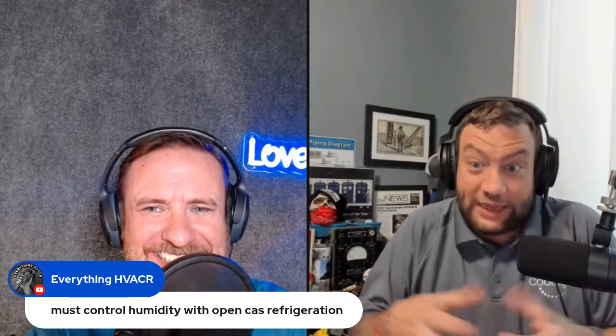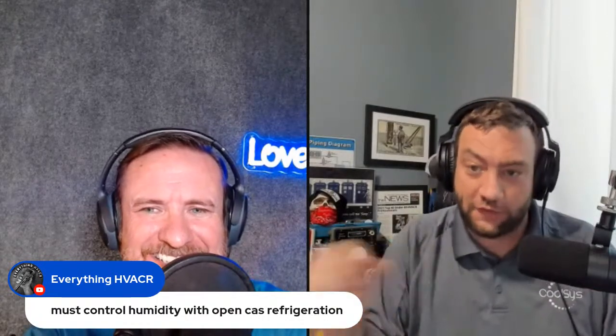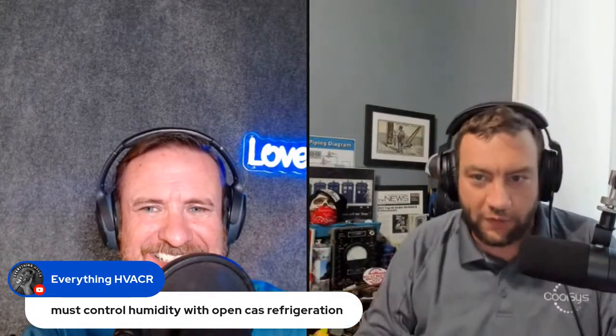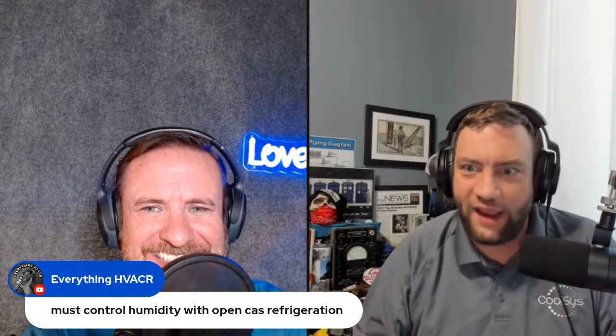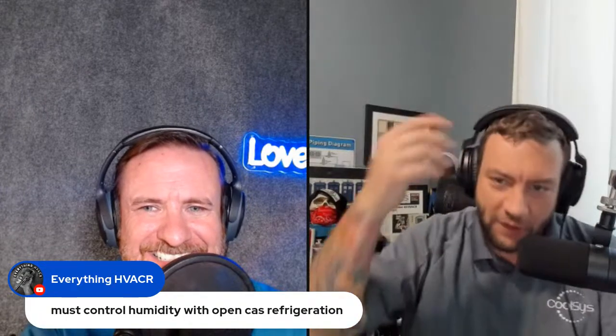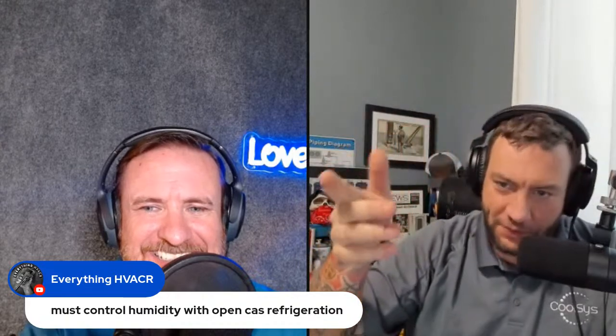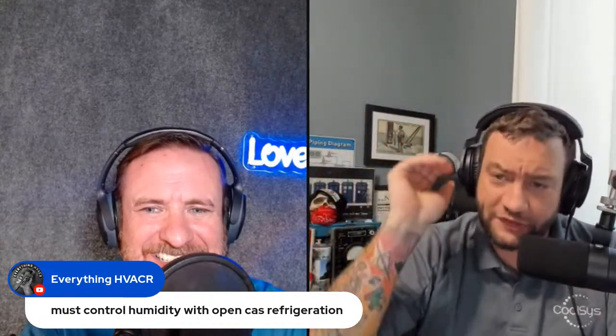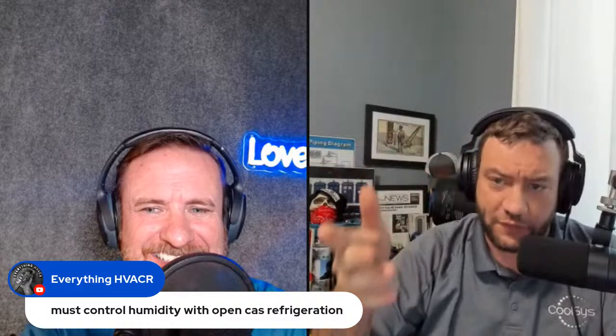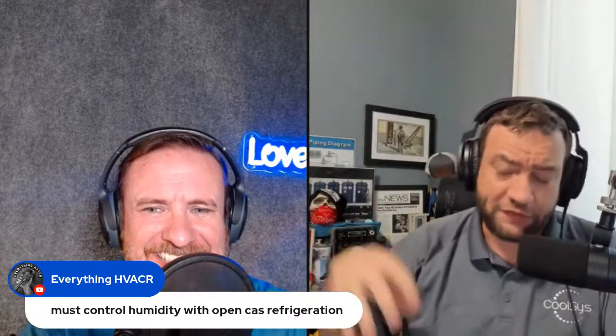It was actually inflated, and you could see it in the air along the seams. I saw metal foil tape over every single seam. I'm like, why is every single seam leaking? So I go up, there's a VFD booster they put on there just to get some additional pressure in this one facility, because it's a fresh air unit.